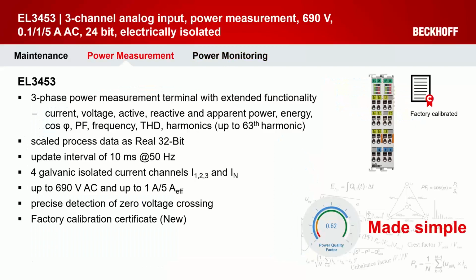So here's the one candidate I explain a little bit more. This is our EL3453. This terminal integrates all power monitoring and power analyzing functions for the voltage level of 690 volt AC three-phase, which is very typical in the wind turbine drivetrain, directly connected to the generator. For easy integration, the customer reads already scaled process data as 32-bit real in standard SI units. That means voltage, amps, watts, and so on.